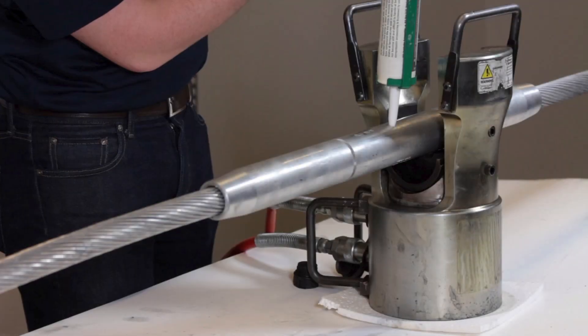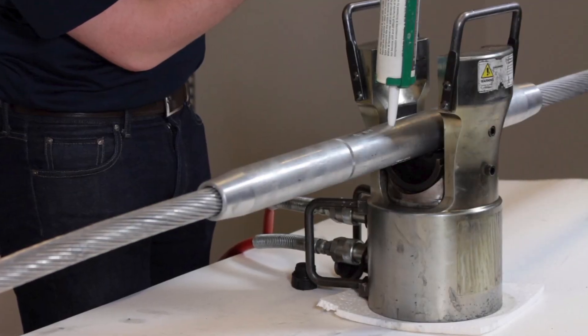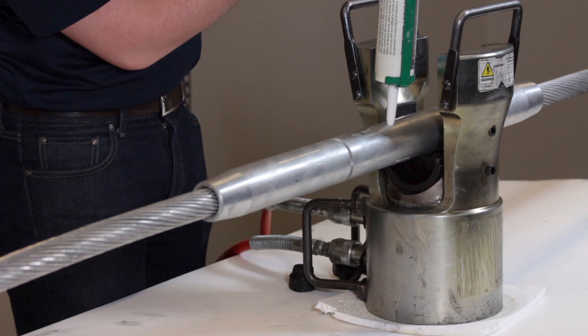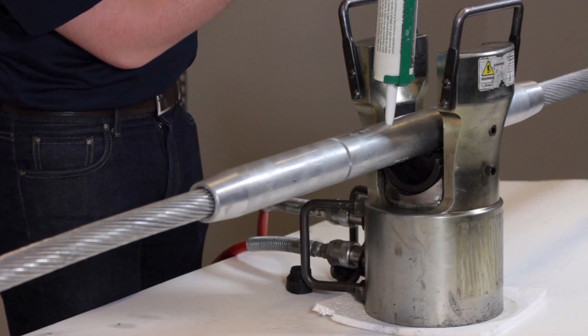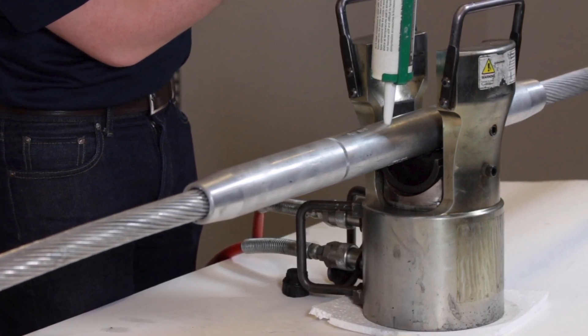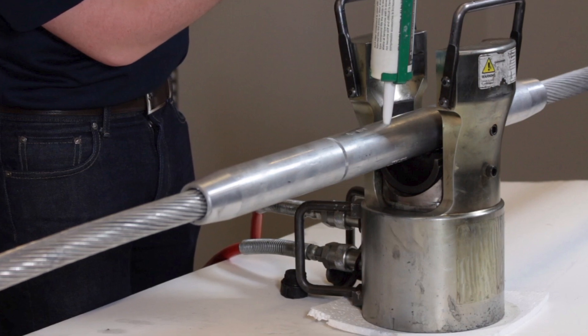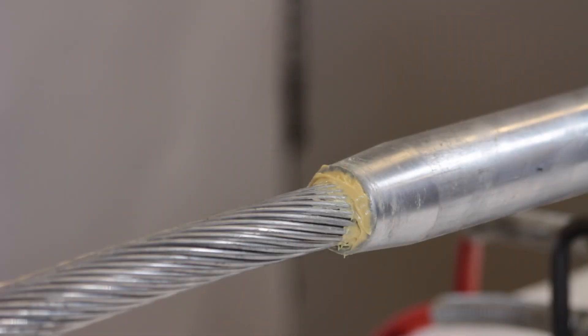Inject appropriate inhibitor compound through the filler hole in the aluminum body. For ACSS conductors, the inhibitor must be rated for temperatures up to 250 degrees Celsius. Cease application when inhibitor seeps out the ends of the hardware. This will continue to ooze out the ends as compressions are applied.